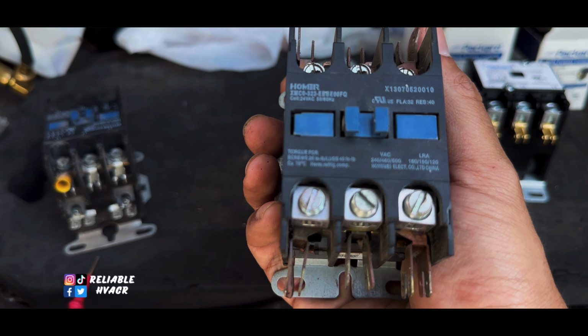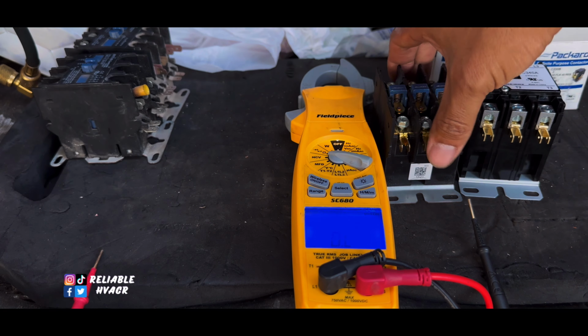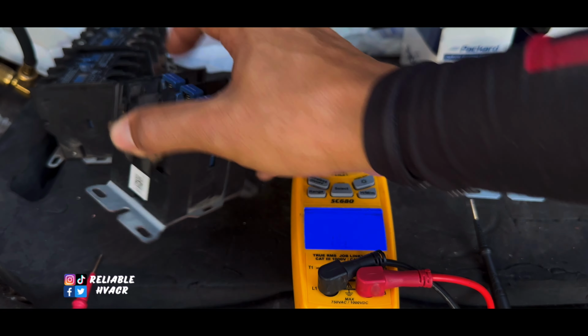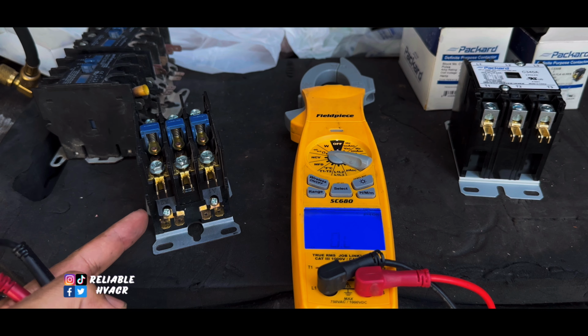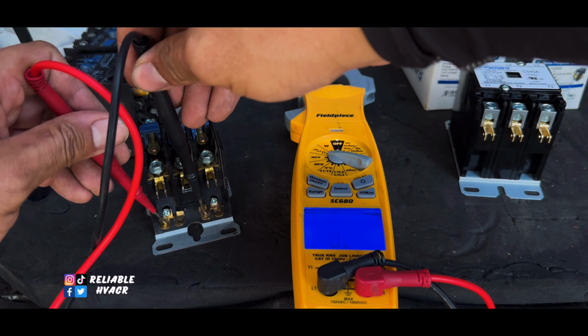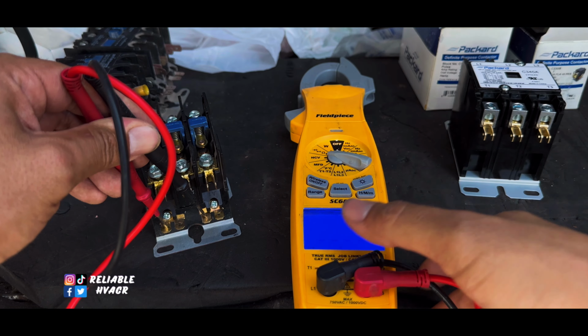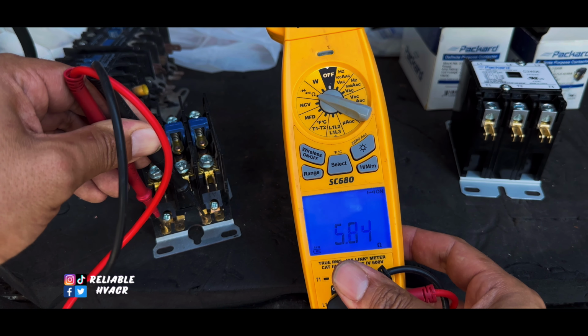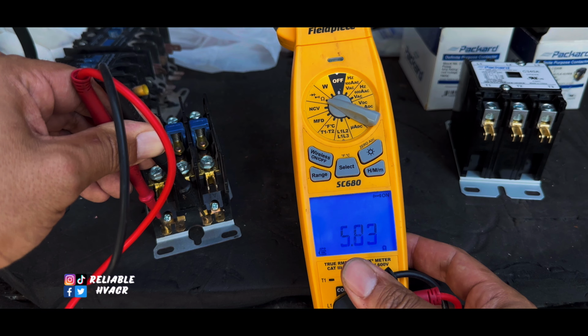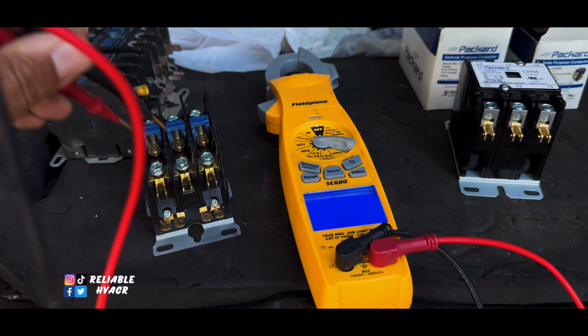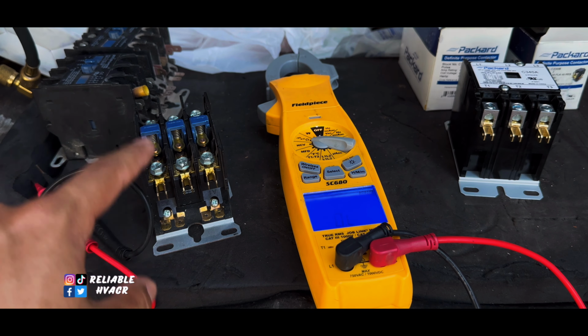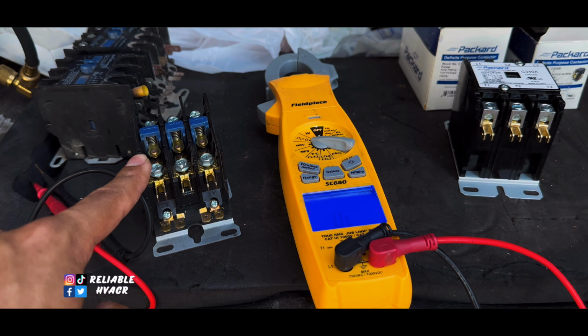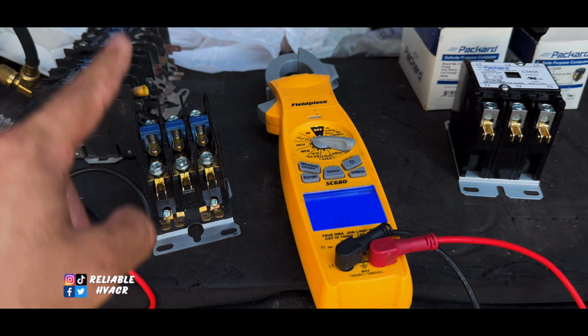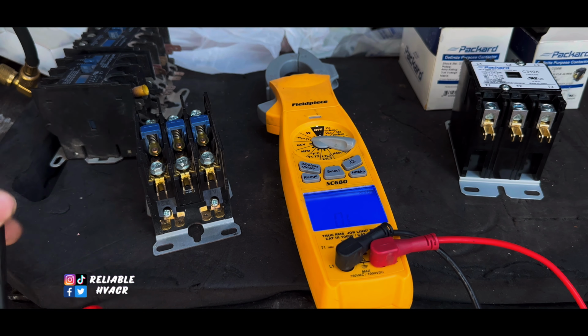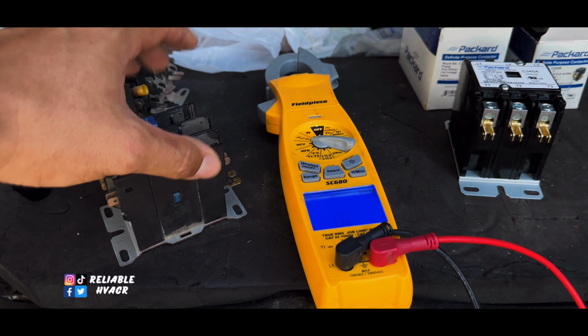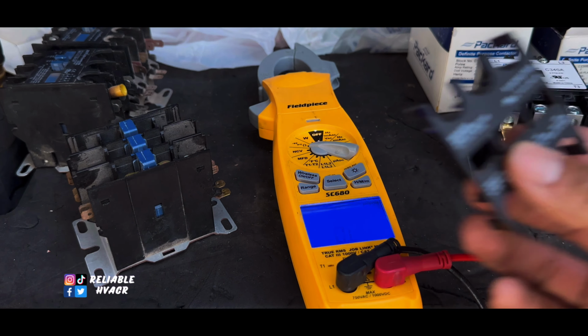This is a 40 amp 24 volt coil. This one is used, but it should be in working condition. I think it was just changed out as a precaution for other repairs, and I saw it there at the shop thrown out. This one reads 5.8 to about 6, which is what I was getting on the ones I checked, and this is the same exact contactor. The unit we had in this video, they both read exactly the same, and then this one read exactly the same. So I'm going to assume that's normal for this contactor.